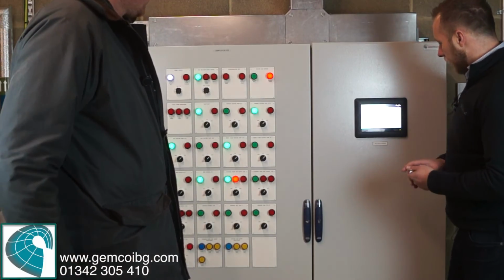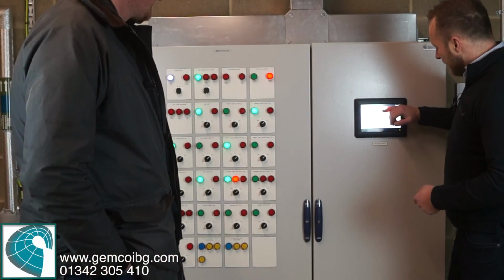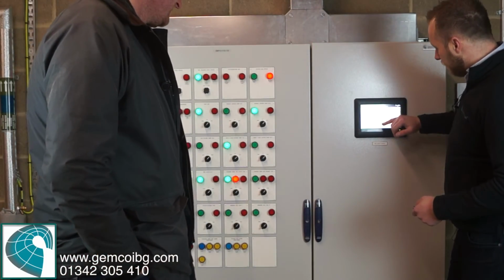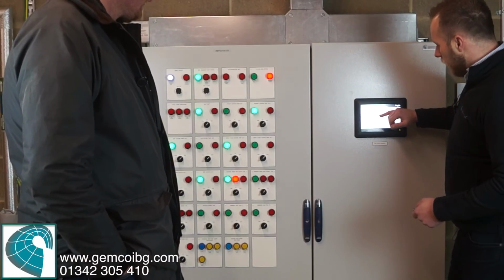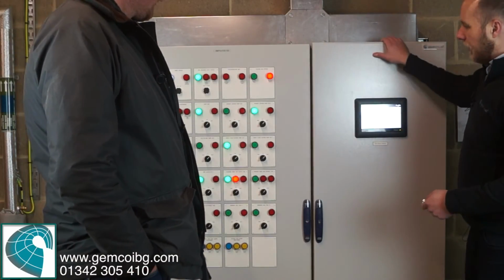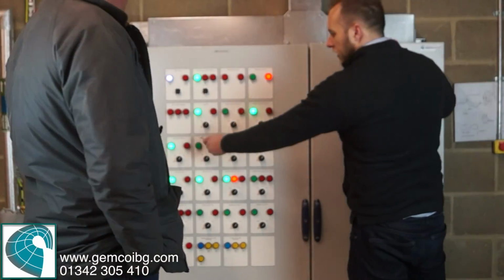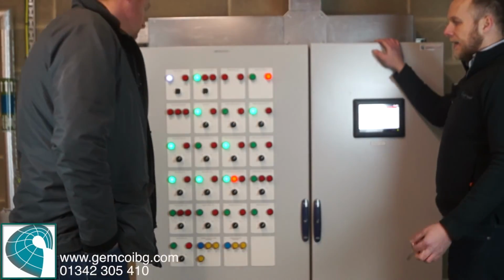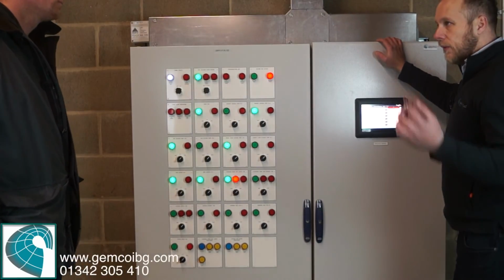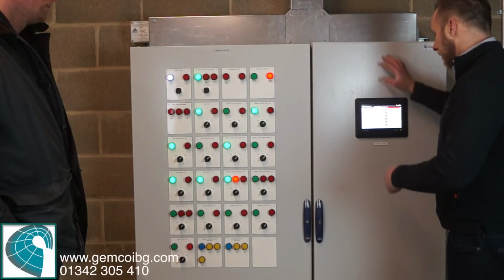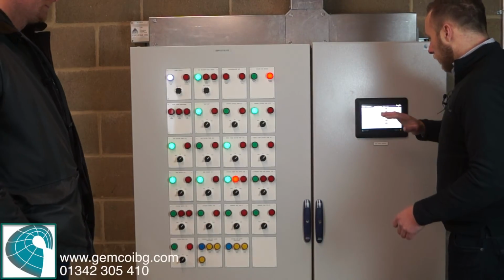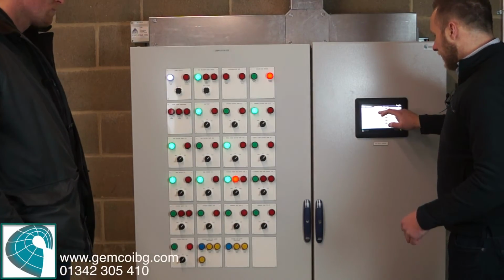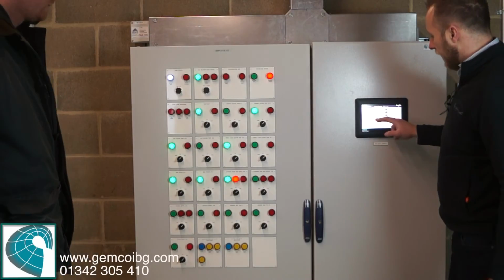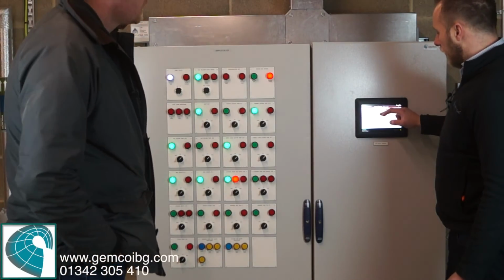As you go into the boiler room, you're going to see all of the temperatures. So this is where you're going to see all the settings. For instance, when I said to you that we monitor the pump that's in duty and there's no flow, so it fails the pump. It starts the second pump. What it'll do is it will fail that pump until you've reset it. An alarm will flash on here, and it will require resetting.